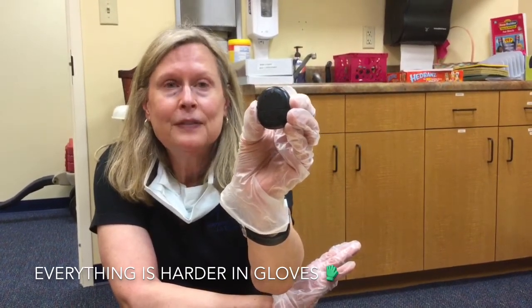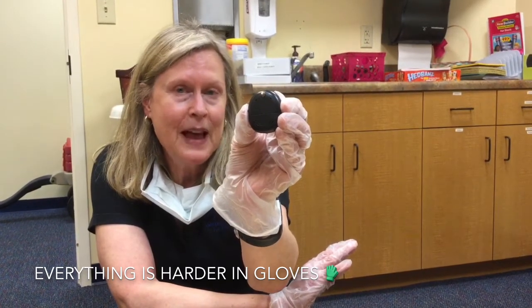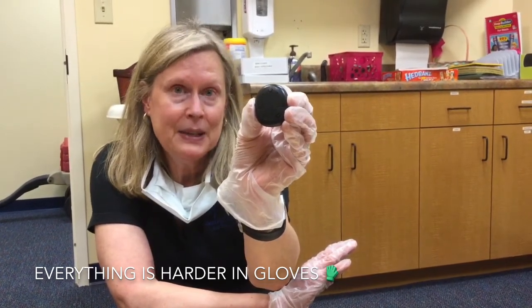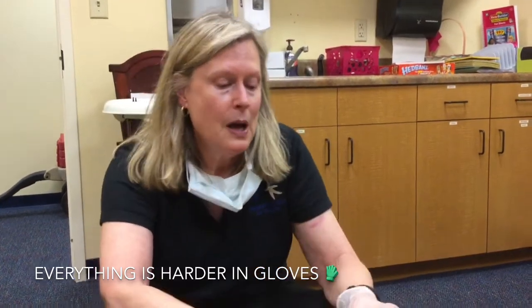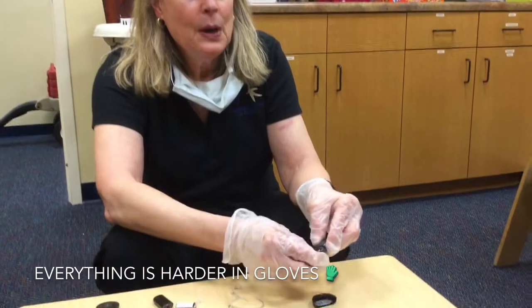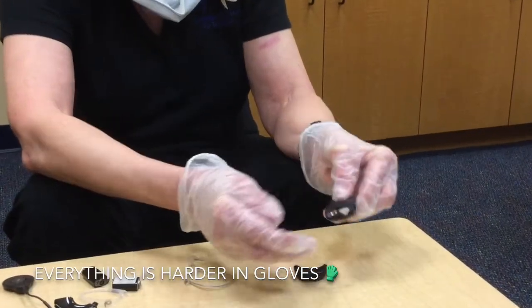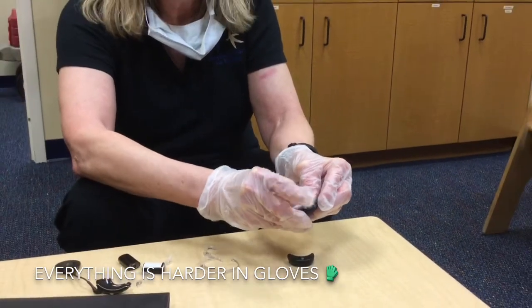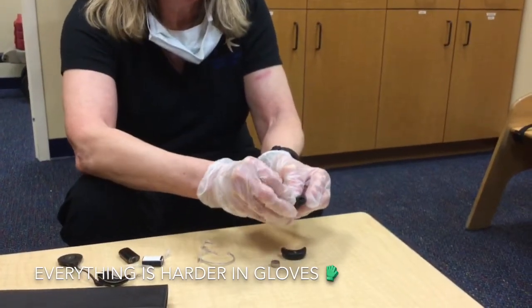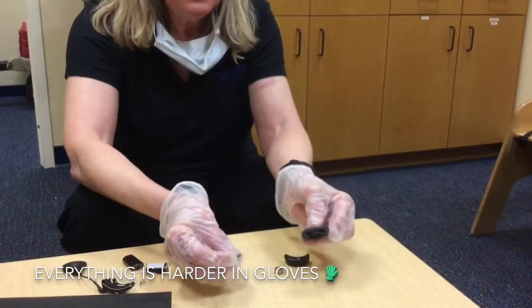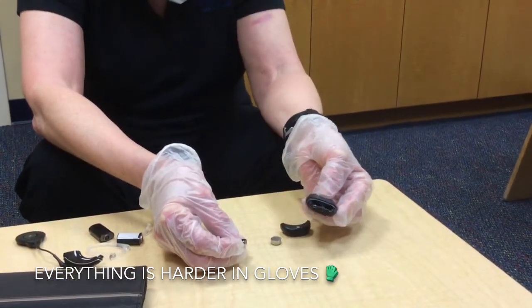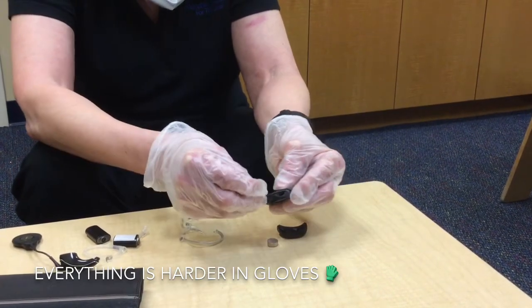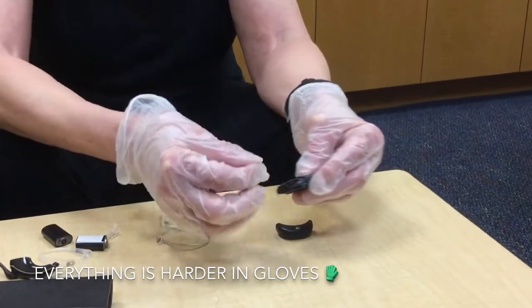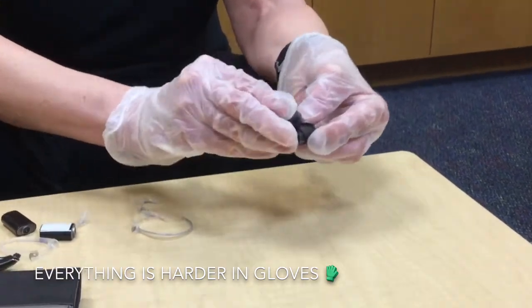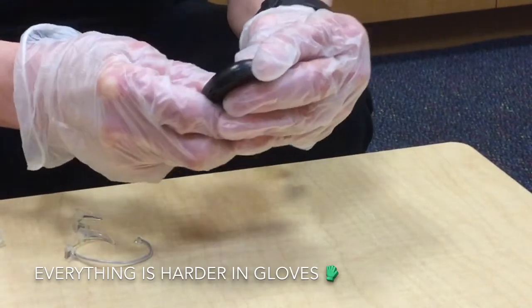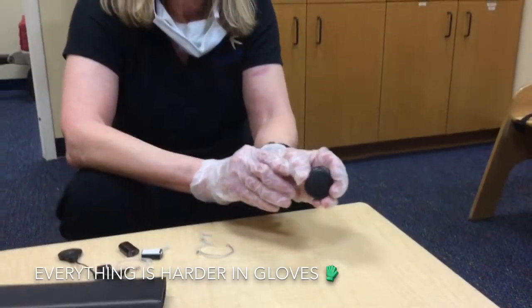If you see a quick flashing light, about double the speed of the slow one, that means you have dead batteries. Open up the Kanso, remove the batteries, and put new ones in. The batteries just pop out quickly. It's kind of hard to do in gloves, but get new batteries, take the seal off the brand new battery, make sure it's good, then put the new batteries in and close the cover of the Kanso. That should take care of any battery issue.